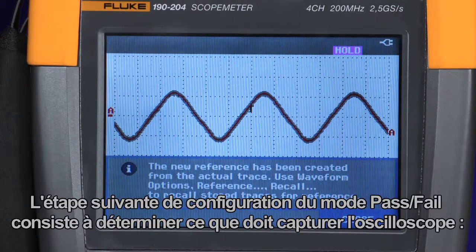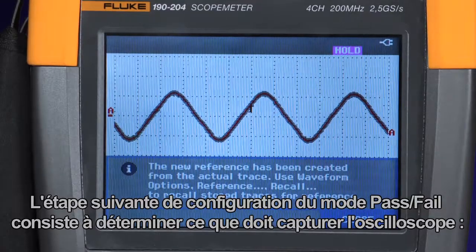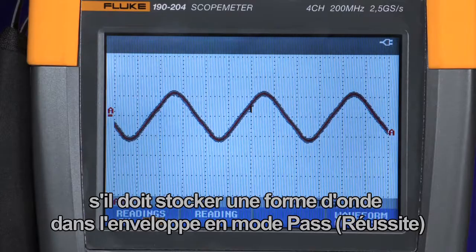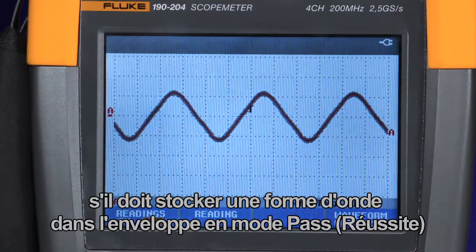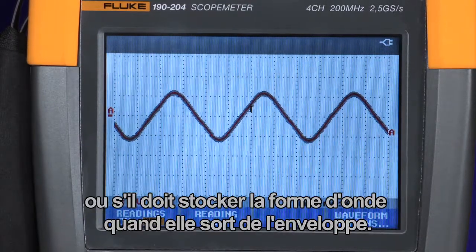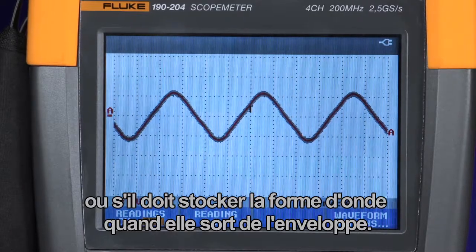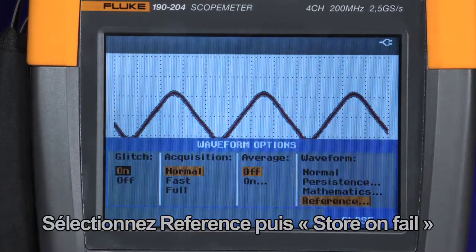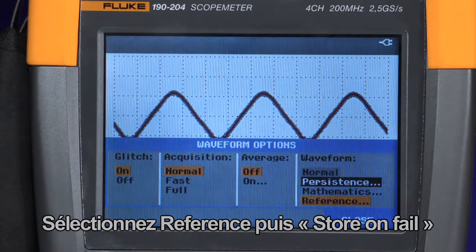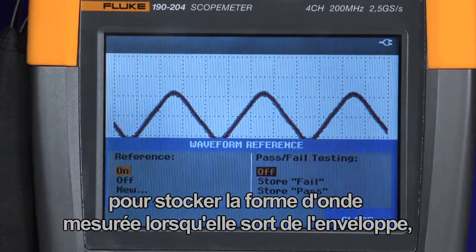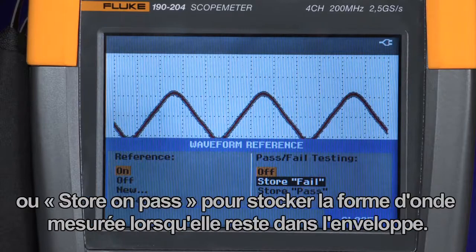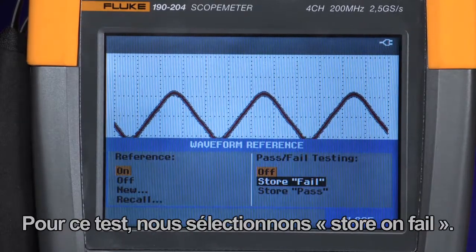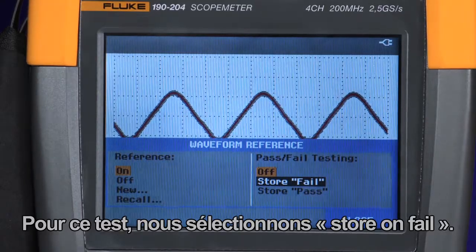The next step in setting up the pass-fail test mode is to set up the oscilloscope to decide what it should capture — whether to store a waveform within the envelope in pass mode, or store the waveform when it exceeds that envelope. Press the waveform option menu, select reference, and then choose either store on fail when the unknown trace exceeds the envelope, or store on pass when it remains within the envelope. For this test, we'll choose store on fail.